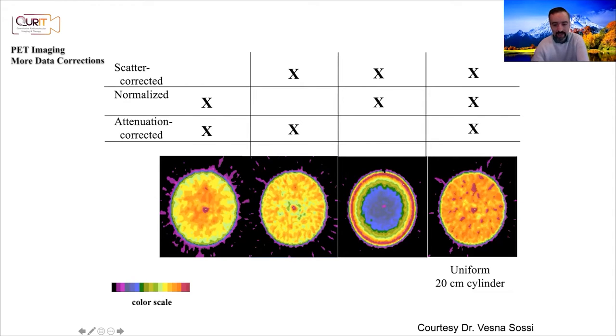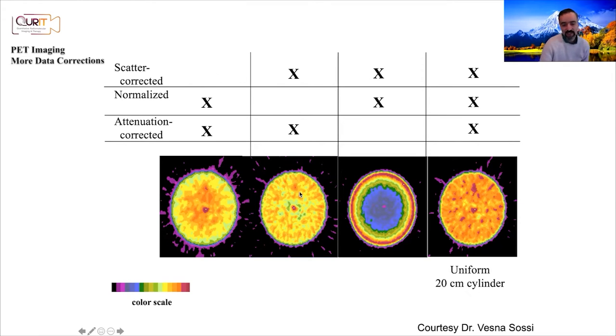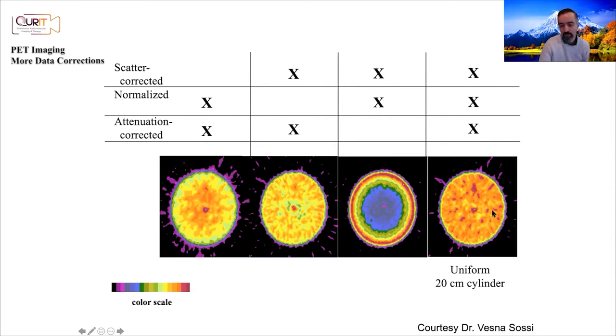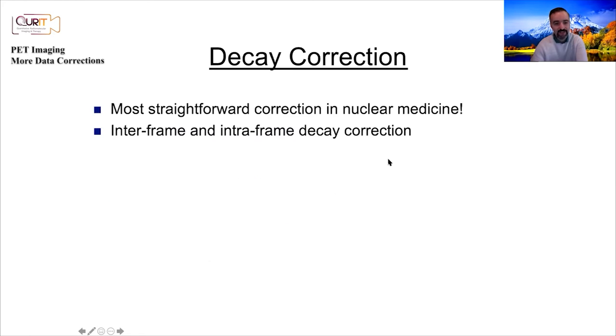Here's an example. If you do not do attenuation correction you get the usual dip we keep seeing. If you perform attenuation correction but not scatter correction you see a hump — you've corrected for attenuation but scatter causes overestimation. Once you correct for scatter but not normalization you may get a non-uniform image. Once you correct for all of them you get a more and more uniform image.